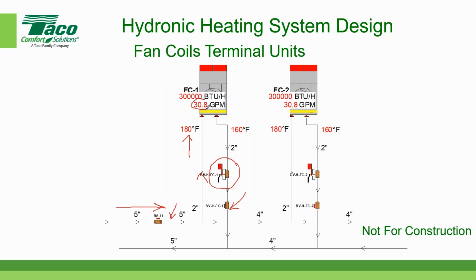gallons per minute. And in this very oversimplified diagram, all of the terminal devices are the same size. And again, not for construction because there's a lot of components missing. Usually for this type of system, there would be an isolation valve perhaps here and here from the main, and that would allow you to shut those valves.